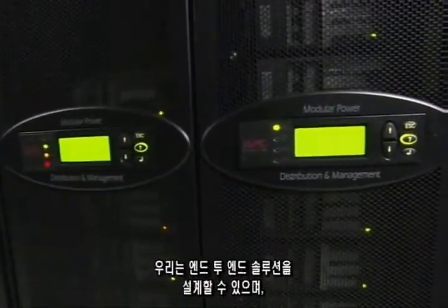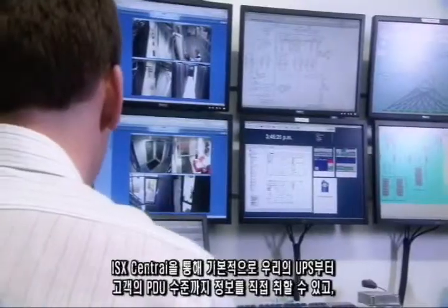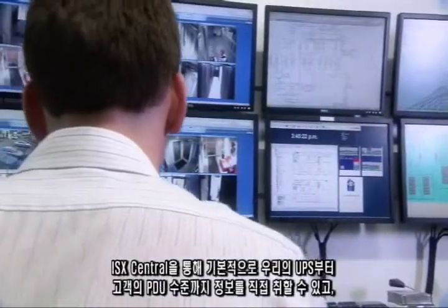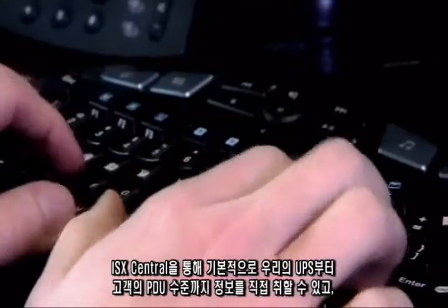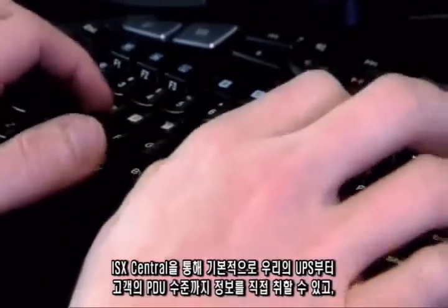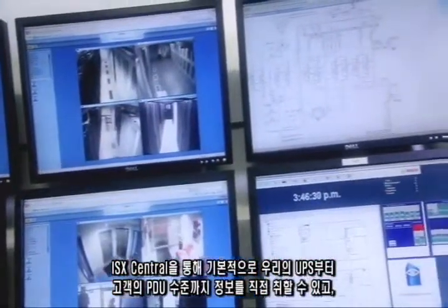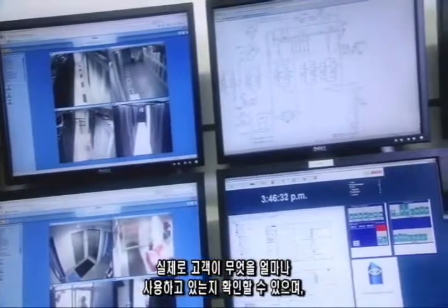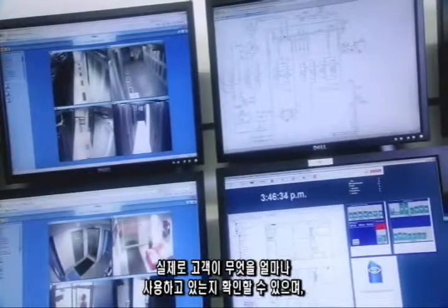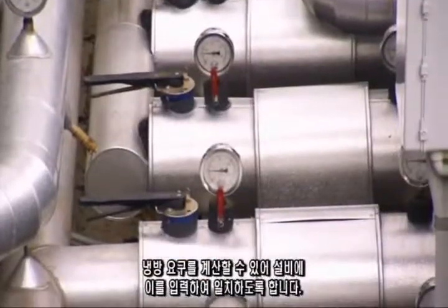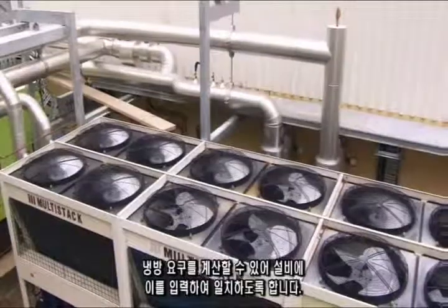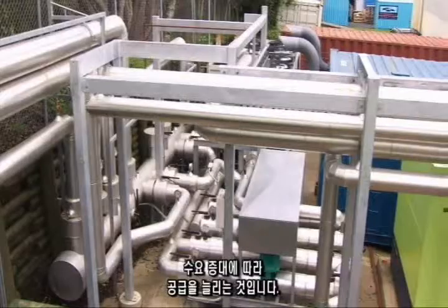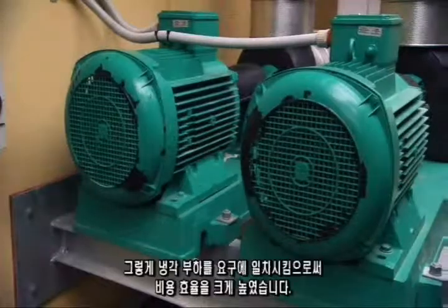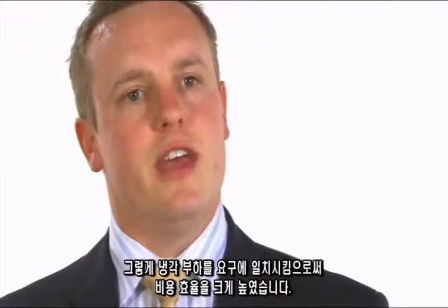We could do an end-to-end solutions design. So through the ISX Central, we were able to basically take right from our UPS down to the customer's PDU level and actually see what a customer was using, and we were able to compare that to the amount of cooling we were putting into the facility to make sure that we were closely matching those. We can grow as the demand increases, so by matching that cooling load to the demand, it's much more cost effective for us.